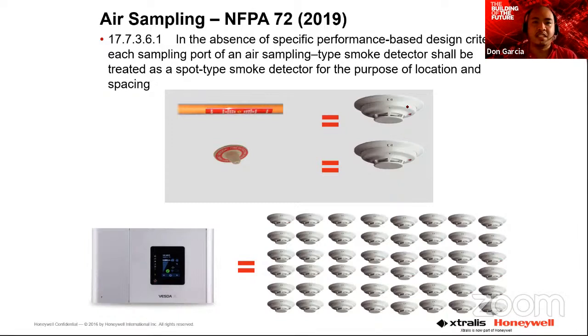Okay? So on the NFPA 72/2019, chapter 17.7.3.6.1, what it says is: in the absence of specific performance-based design criteria, each sampling port of an air sampling type smoke detector should be treated as a spot detector for the purpose of location and spacing. Basically, if your hole is located in a facility, it will act as a spot detector. That means whatever the capability of a spot detector is, the hole you use in the pipe of the VESDA has the same capability, but with advanced technology.